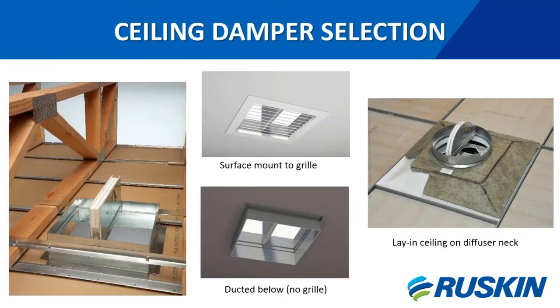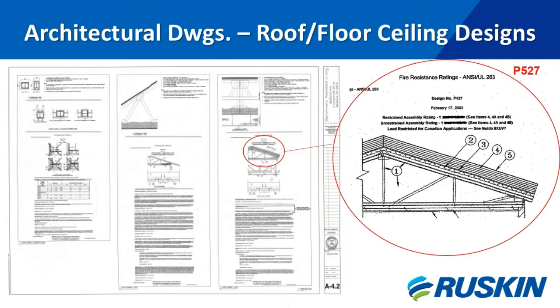When selecting which CFD to use, start with the architectural prints, which should show and call out a roof-ceiling or floor-ceiling plan and description. In most cases, a design number is called out on the drawings. This design number is the most important item on the drawing — with this number, we can look up the design and determine which damper should be used in that assembly.